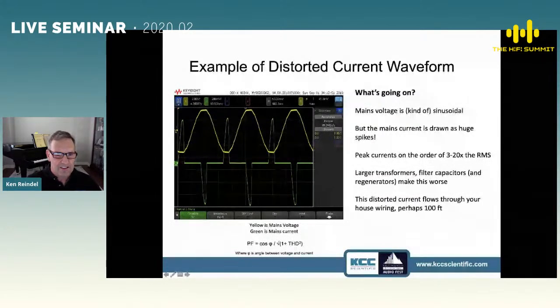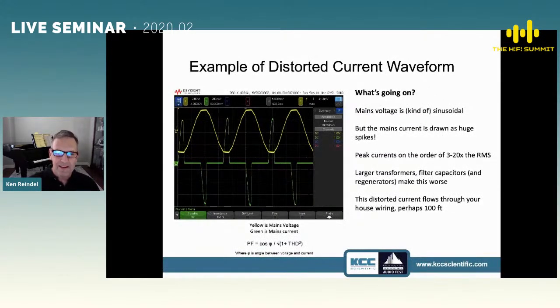Is it at least a possibility that this could be creating noise somewhere, this current? Well, everybody looks at the voltage waveform and how pure it is and never looks any further. But if you actually look at the current, you realize what a mess is being made of our environment with this kind of current, these kind of current spikes and the harmonics that they generate, and where else they get into magnetically. So this is a real issue.